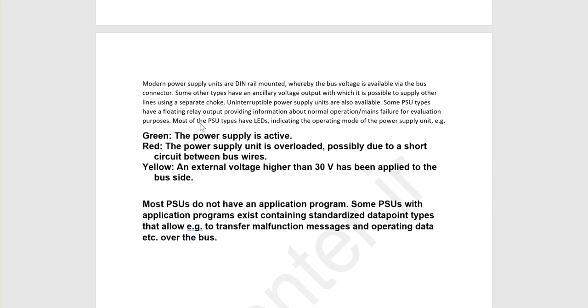Okay, so about the color of the LED, I said if it is green, it means the power supply is working normally. If it is red, it means the power supply is overloaded, for example, short circuits happen. When you press the reset button, if you always do the short circuit, the red LED will be on. The yellow means an external voltage higher than 30 volt has been applied to the bus device, bus side.